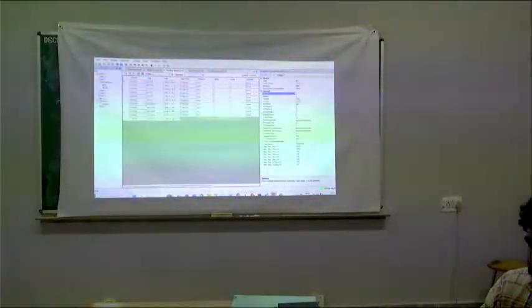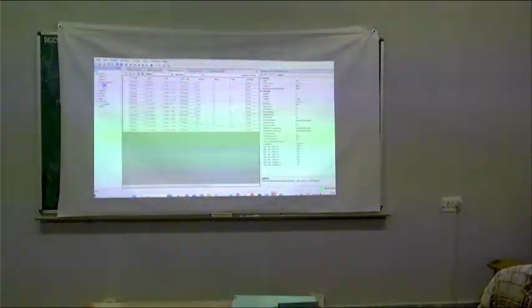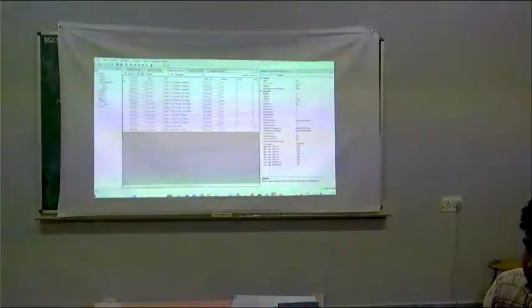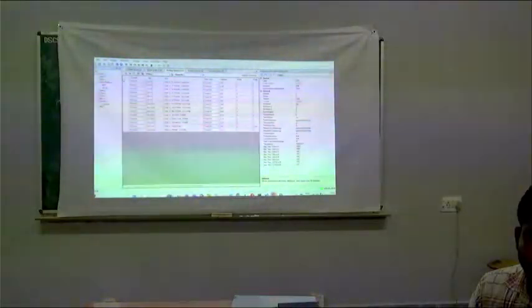Next, you go to that MFT. Now here, from the manufacturer we have got the Modbus mapping address details from Accord, for example. Accord is the name of the company which is manufacturing the meter. He would have given me the Modbus mapping details. Seeing those mapping details, he has told me that at address 147 he is sending the R phase current, and Y phase current is 149. Okay, so I specify all those addresses there. Then it will connect to this device, go to the memory of this Accord meter and read those values, and that is fetched to my gateway. Clear? Huh?